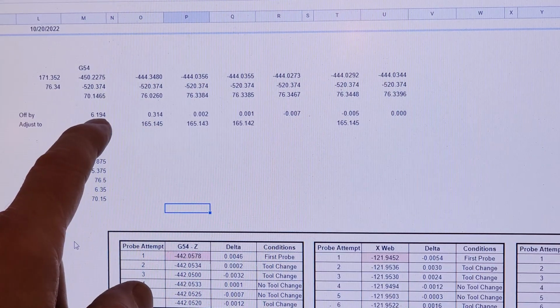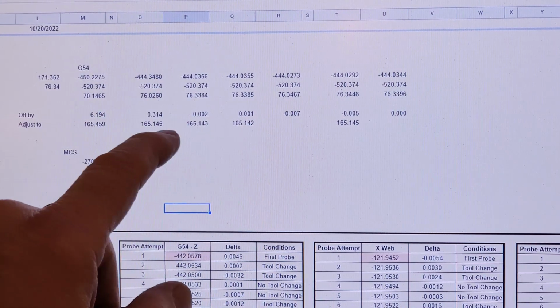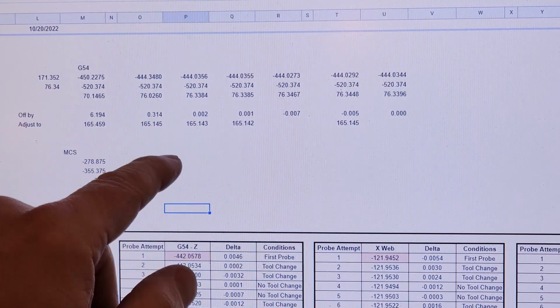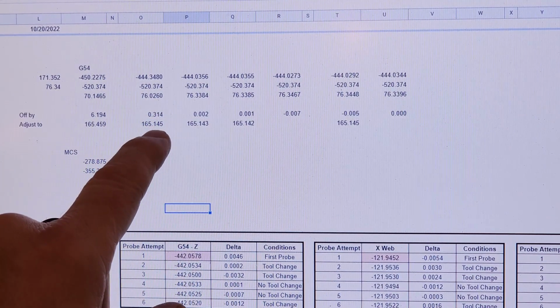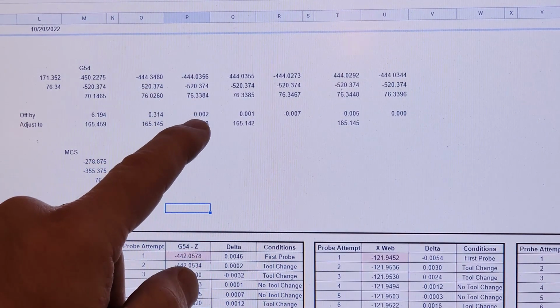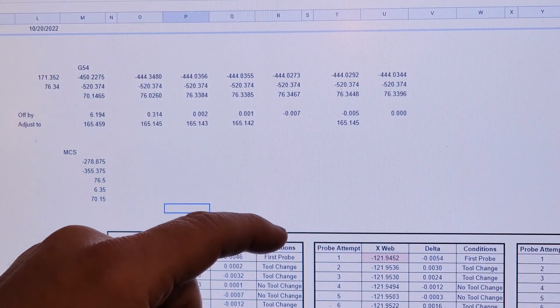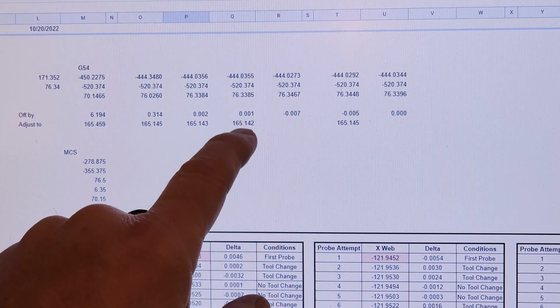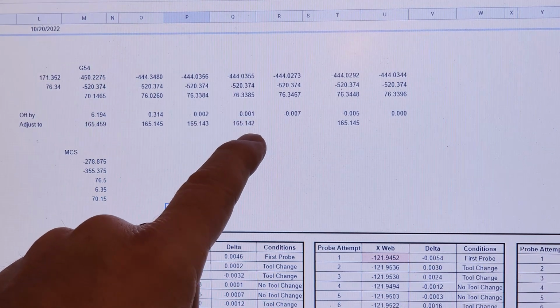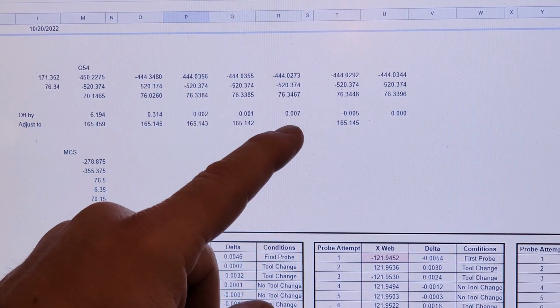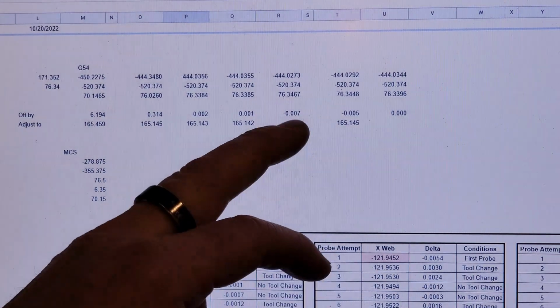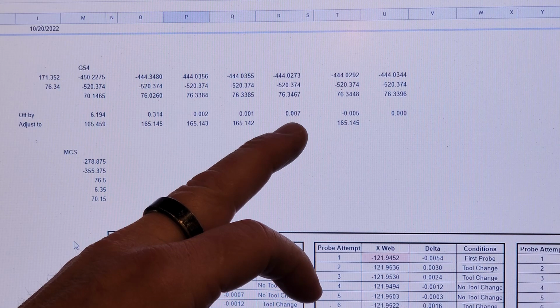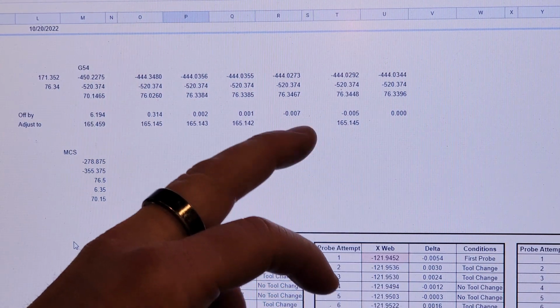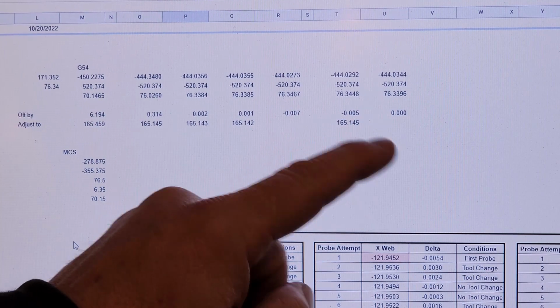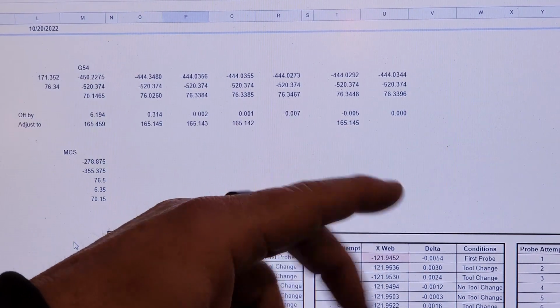So I put in the new offset, ran the probe again, and it was off by 0.3 millimeters. I had a new calculation, put in a new offset of decimal 145, and was off by 2 microns. Adjusted for that, was off by 1 micron. Now I'm chasing zeros. I adjusted for 1 micron, and all of a sudden I'm off by 7 microns in the other direction. I ran it again without adjustment. I'm off by 5. So I just flipped it right back to 145, and I was 0.